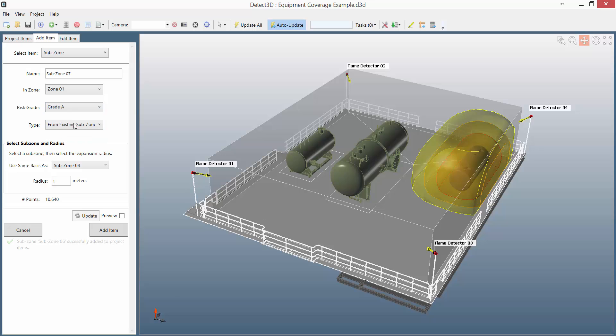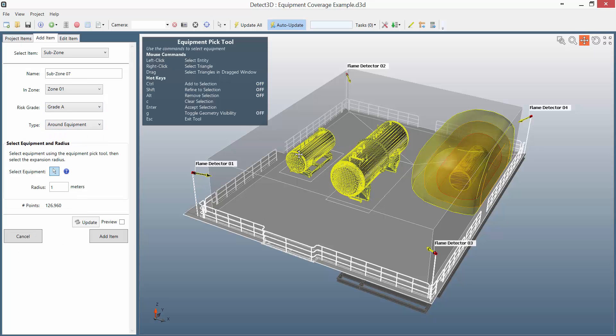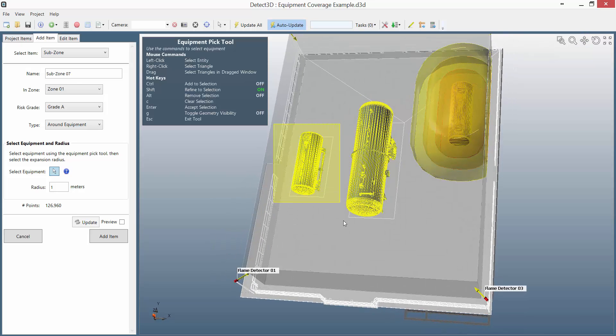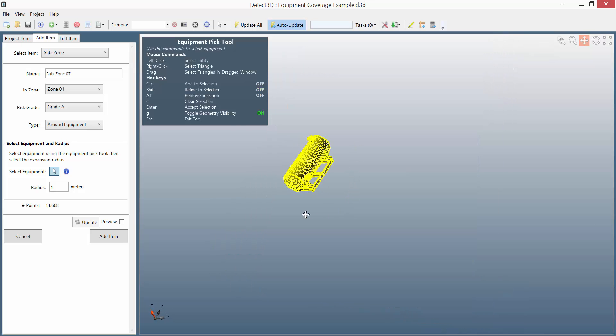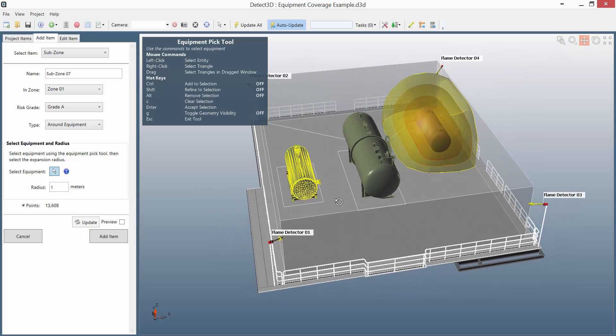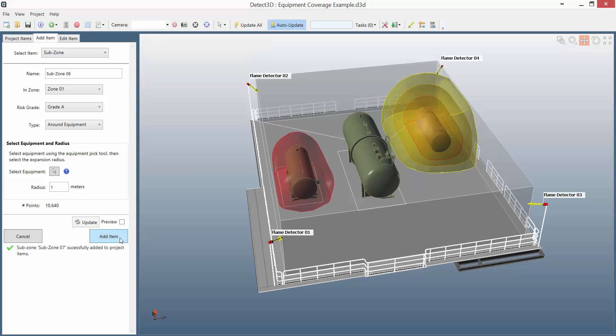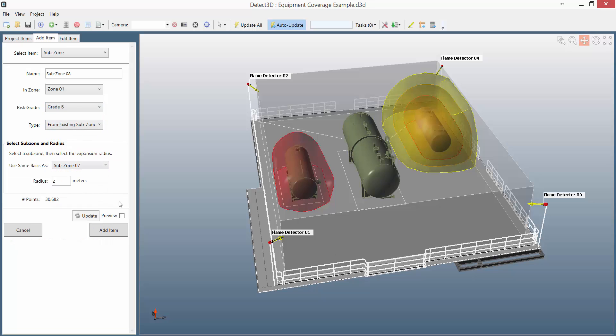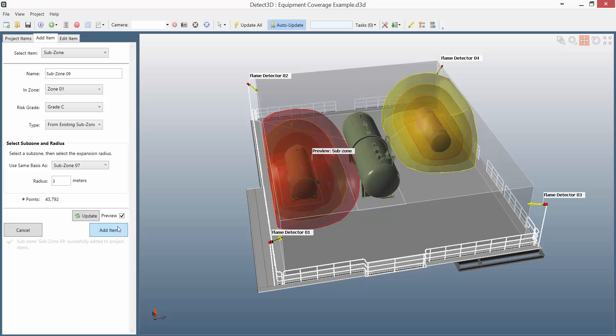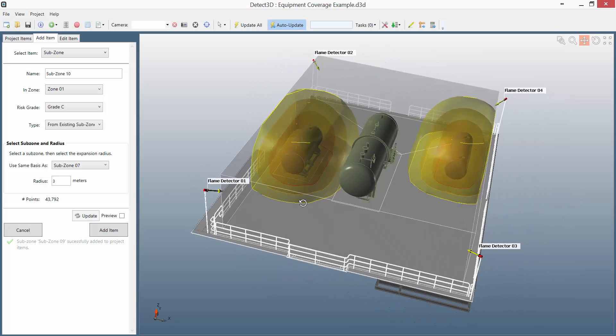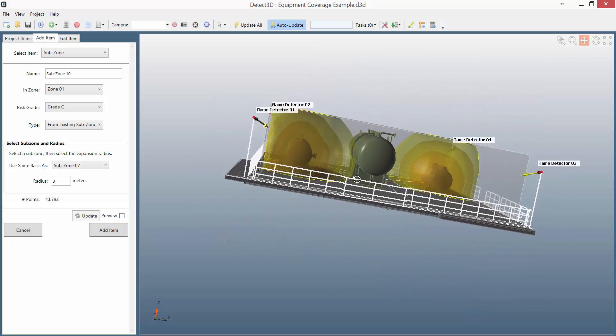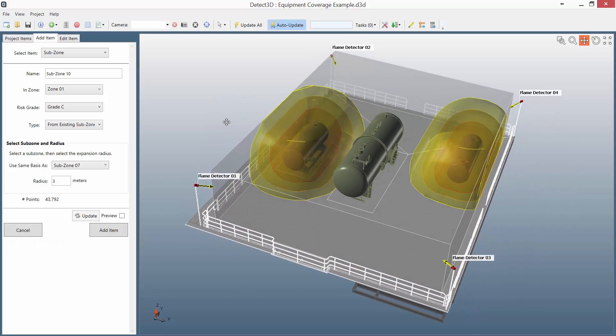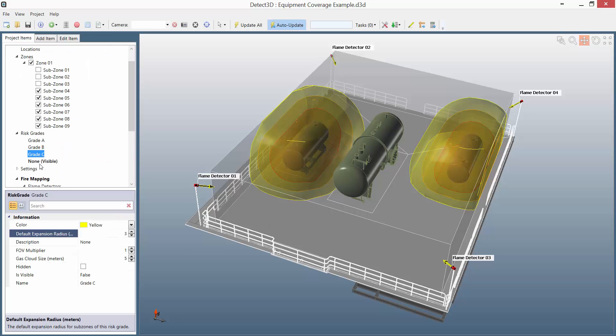So I'm going to look next at the final vessel, again using the equipment pick tool to initially select and then refine. I can check my selection here, and then I'm going to add a grade A subzone around that one at 1m, grade B using that first subzone as a base, and then the final one at grade C. Now in that very short space of time to set this up, I now have nine subzones in the zone, and I know the coverage for each fire size at each radius for all the equipment items that I'm interested in.